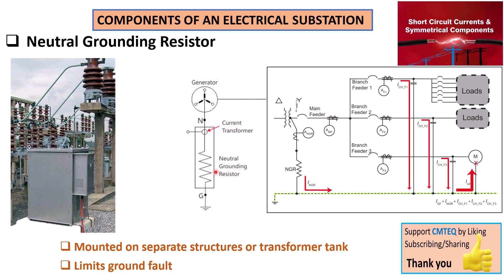We also have the resistance type — that's basically the one we're looking at here — where you implement a resistance between the neutral point and the ground. This resistance limits the fault current to a value that is safe and will not cause trouble. But remember, that limitation must still allow the current transformer to detect and operate. If the current falls below the CT's detection threshold, you are defeating its purpose and eliminating the circuit breaker's ability to interrupt the fault.